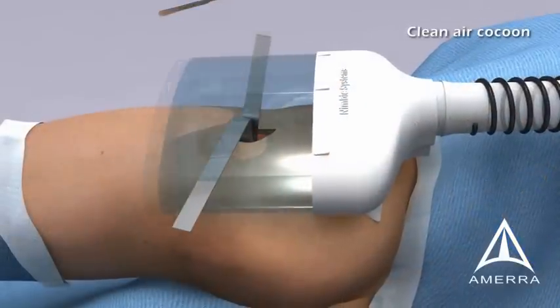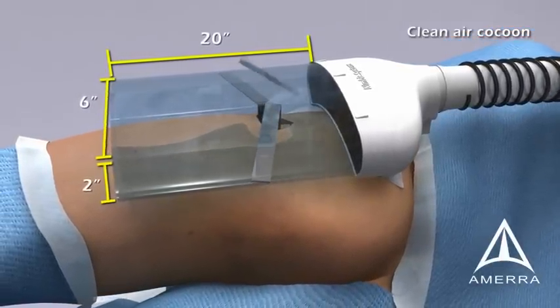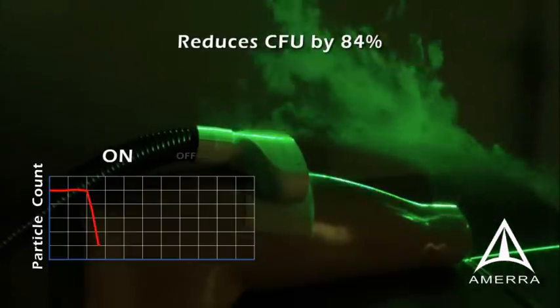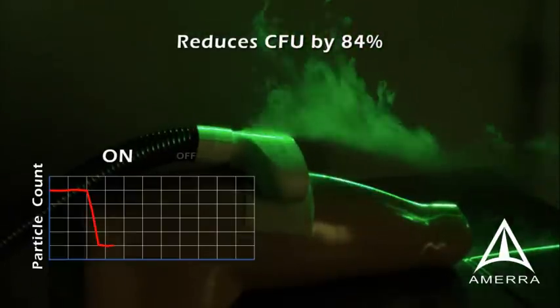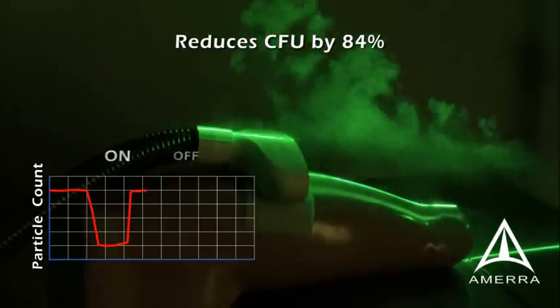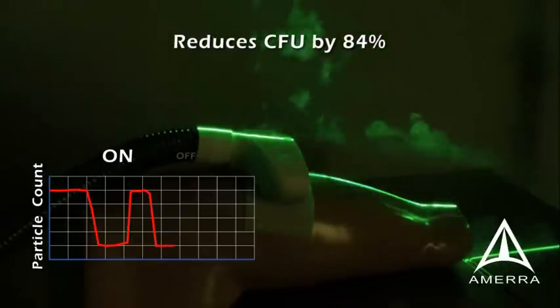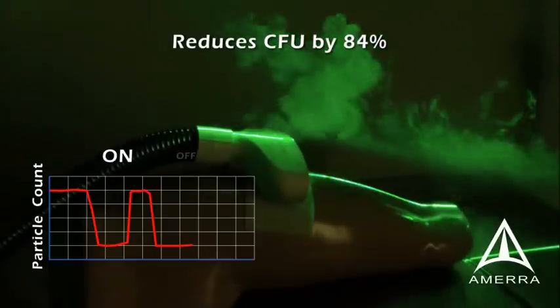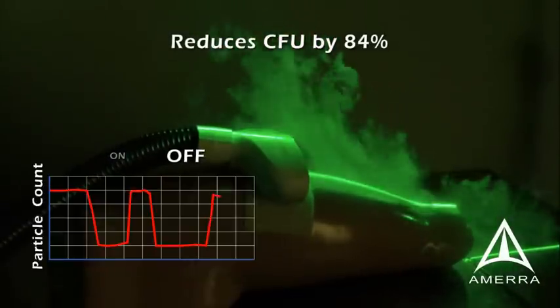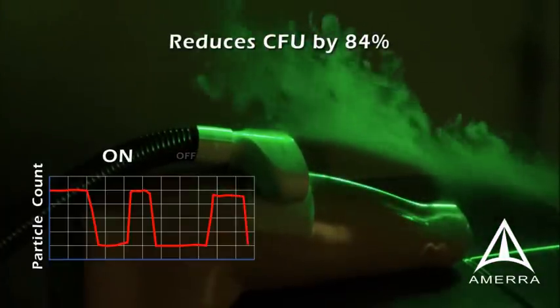The clean air cocoon produced by the AVS creates a protective environment of 6 by 20 inches with a 2-inch depth. Particle counter analysis shows that a surgical incision environment may contain many thousands of bacteria-carrying particles per cubic meter. As the AVS airflow is turned on, the system aggressively reduces the particle count and presence of microorganisms by over 84%. The AVS accomplishes this even during highly dynamic procedures such as hip arthroplasty, greatly reducing the presence of potentially infection-causing organisms.